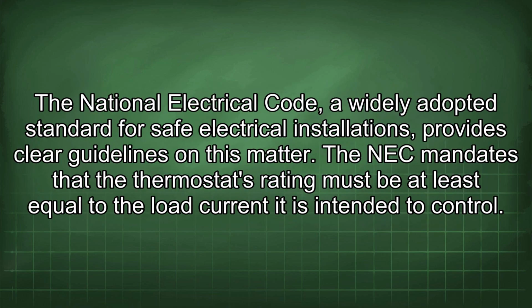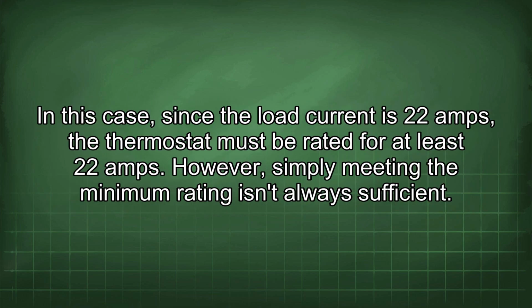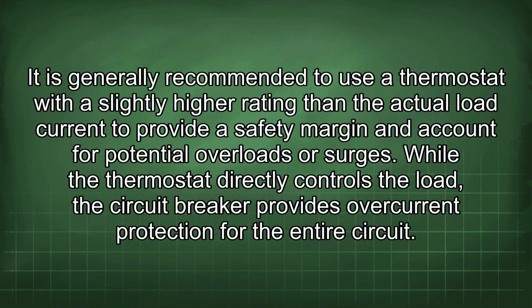The National Electrical Code, a widely adopted standard for safe electrical installations, provides clear guidelines on this matter. The NEC mandates that the thermostat's rating must be at least equal to the load current it is intended to control. In this case, since the load current is 22 amps, the thermostat must be rated for at least 22 amps. However, simply meeting the minimum rating isn't always sufficient. It is generally recommended to use a thermostat with a slightly higher rating than the actual load current to provide a safety margin and account for potential overloads or surges.